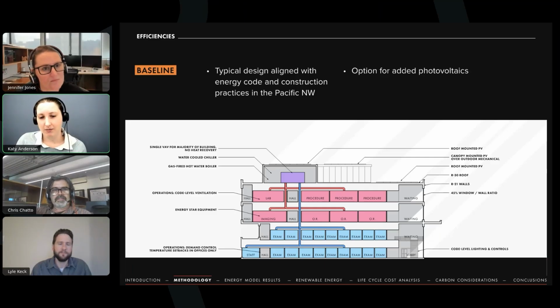So the baseline system, the majority of spaces are served by a single VAV, so return air system air handler with zonal reheat. And there are some exceptions to this, some back of house spaces that are served by fan coils, like electrical mechanical rooms and an IDF room. But for the vast majority of areas, it's just one air handler. And this is a baseline because it is a lower expense mechanical system. It meets code, but as we'll talk later, there are some big downsides in terms of controllability and operations that have energy impacts. So we assumed Energy Star equipment, which in our experience does not have a cost premium.